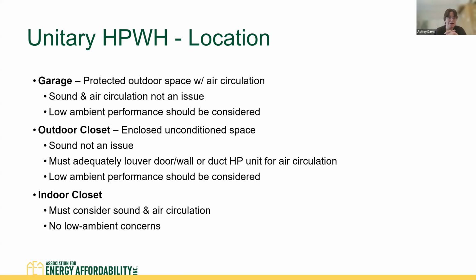Outdoor closets are another common location. This again is an enclosed outdoor space where you probably don't have to worry too much about sound, but because the space is smaller, there's less opportunity for natural convection of the air, and so you will need to intervene with a ventilation strategy, whether that be louvers on the doors with the exhaust pointed at a louver, or ducting the unit for proper air circulation. And again, when you're outside, you've got to think of that low ambient performance.